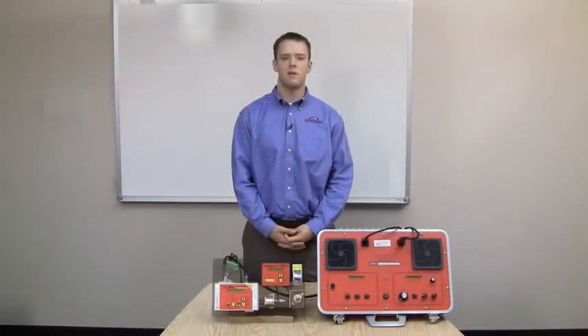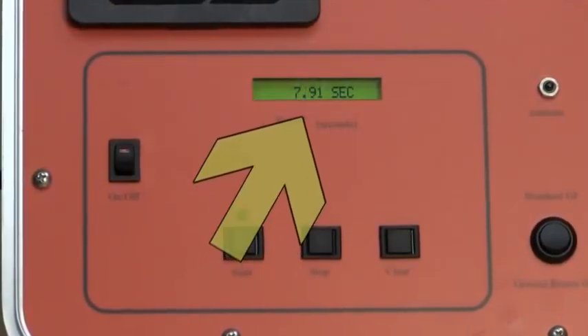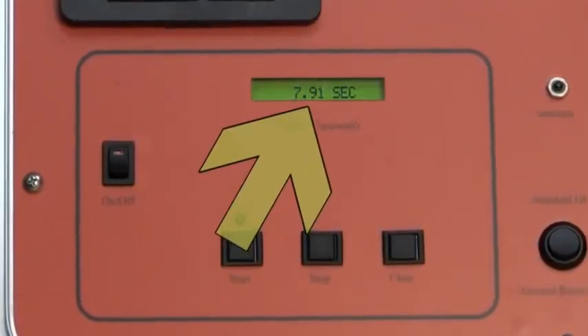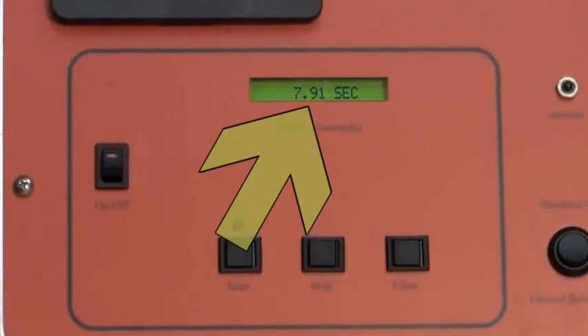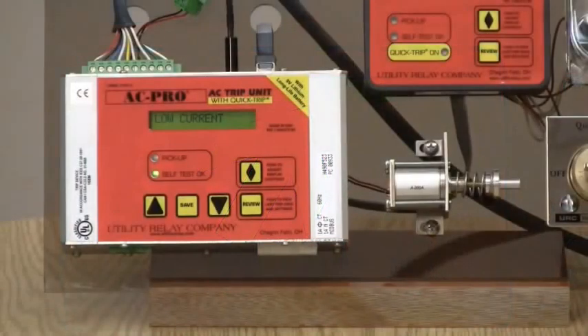As you can see, the AC Pro fired the actuator and stopped the test set. The test set timer reads 7.91 seconds, which is well within the tolerance band for the expected trip time of 8 seconds. The AC Pro saves the data from the most recent trip in non-volatile memory. This data includes the type of trip and the individual phase currents at the time of the trip.